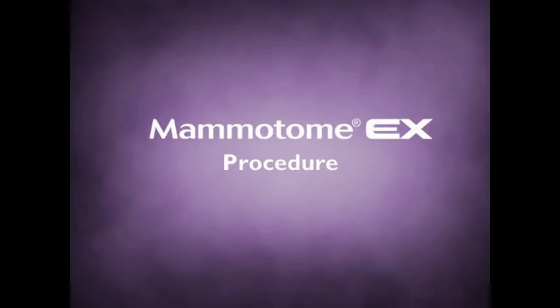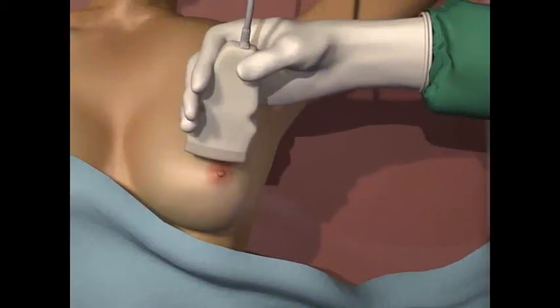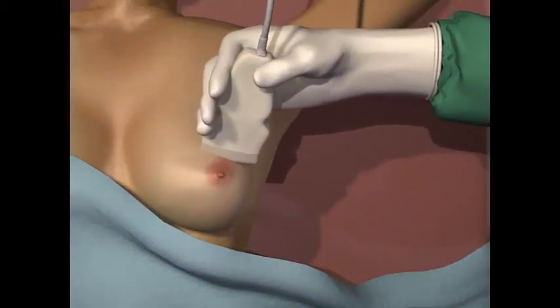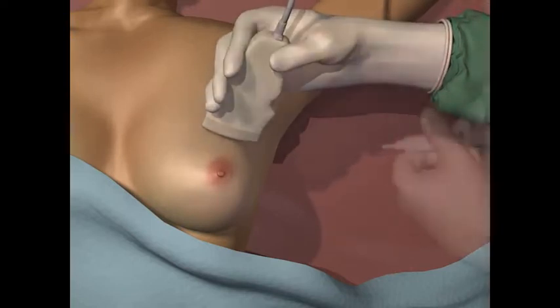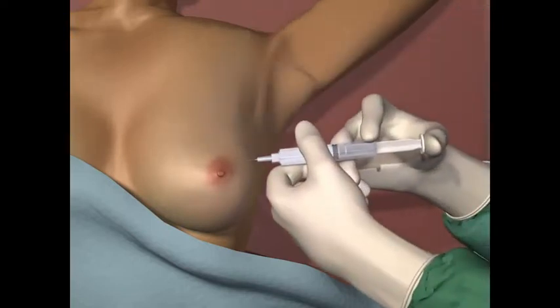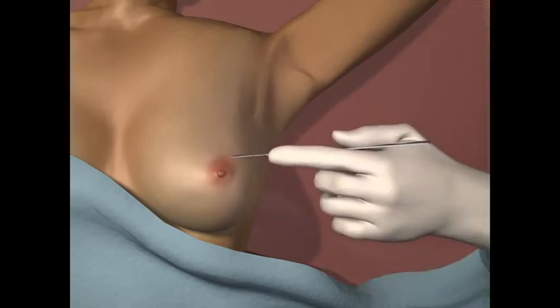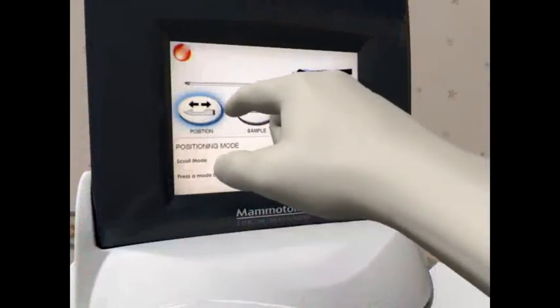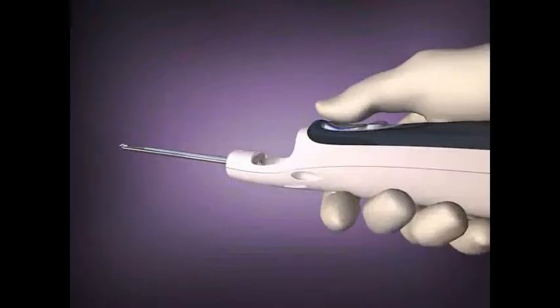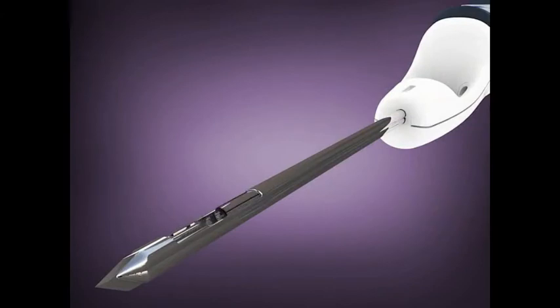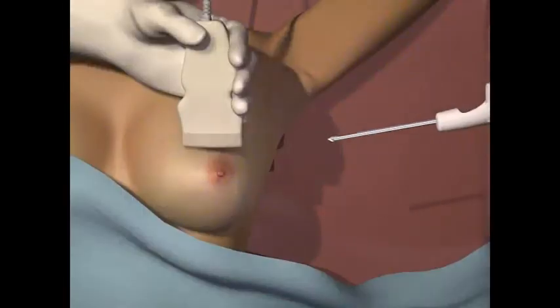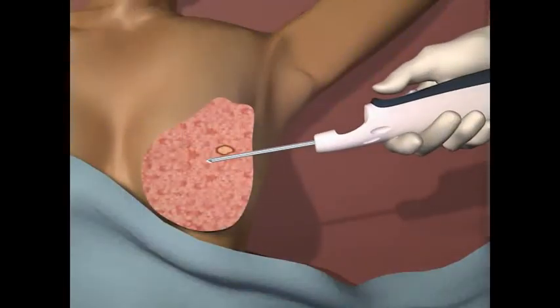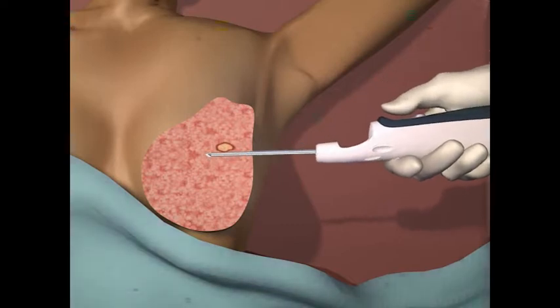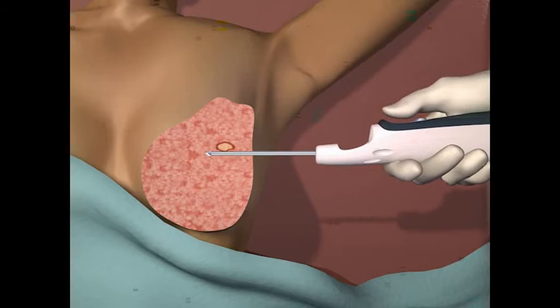Mammotome EX Procedure. Scan the breast with an ultrasound transducer to locate the lesion. Clean the breast, anesthetize using both a skin wheal and deep anesthesia, and make a skin incision. Press the position mode on the Mamatome screen and press the forward button to close the sample aperture. Insert the needle into the breast at an angle to the transducer and position the sample aperture under the lesion. You may want to drop your elbow to lift the lesion.